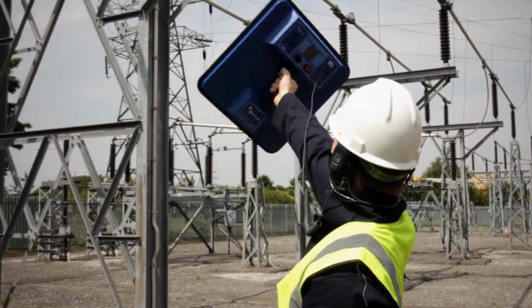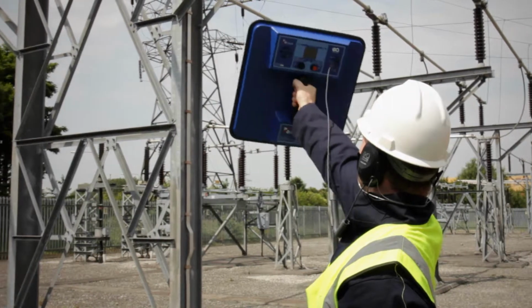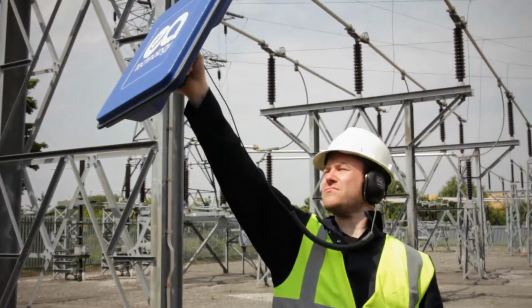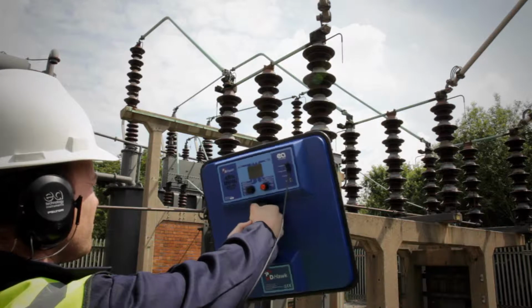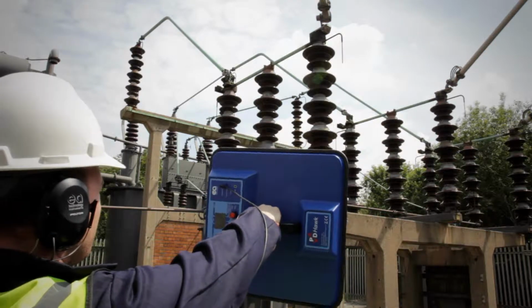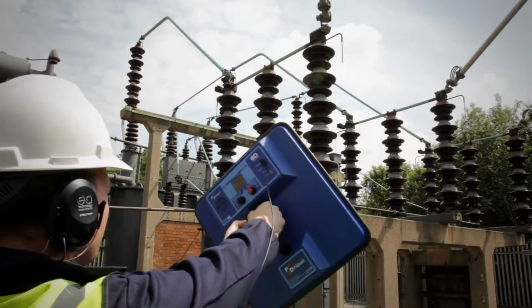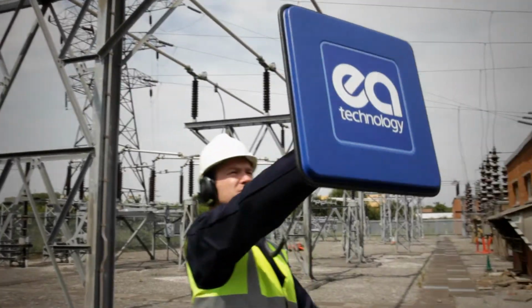The first step is to do a general sweep, scanning for all types of radio emissions. Rotate the instrument to allow for polarity and find the strongest signal. And a whole switchyard can be scanned for PD in minutes.